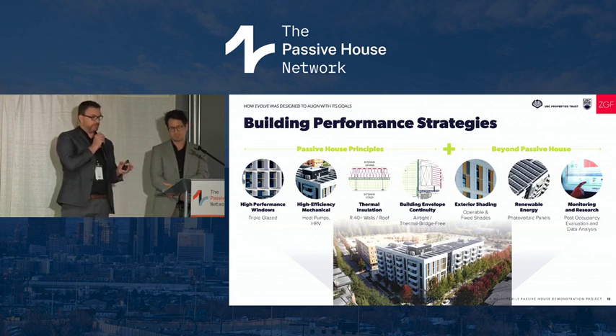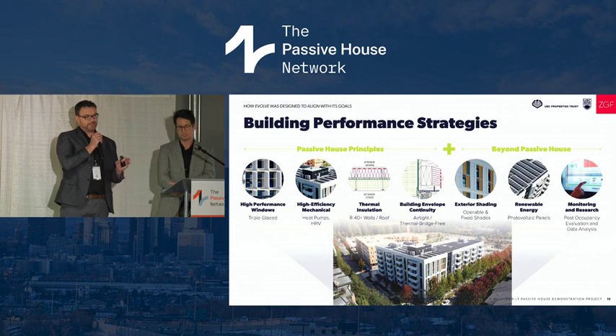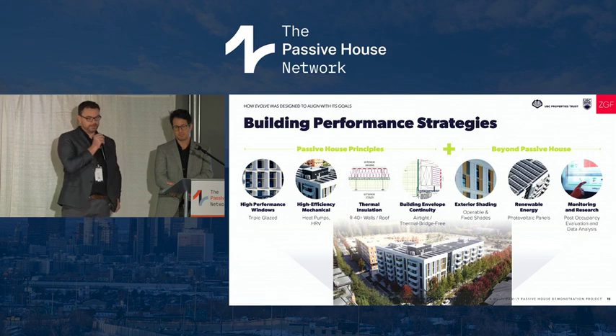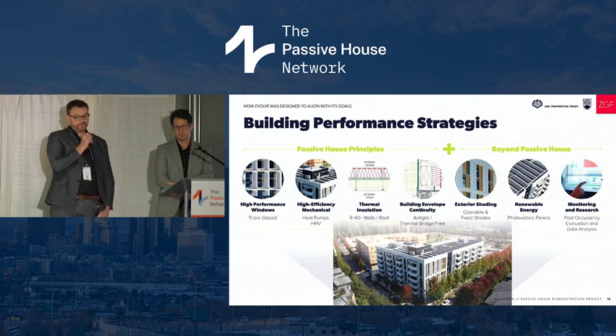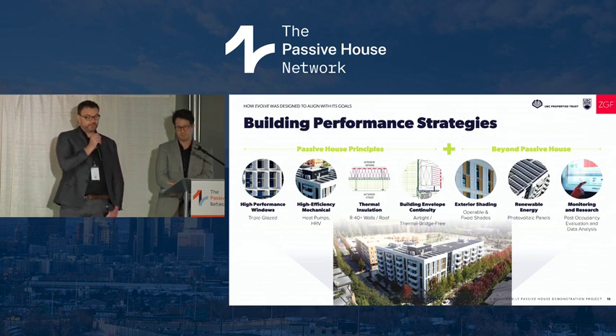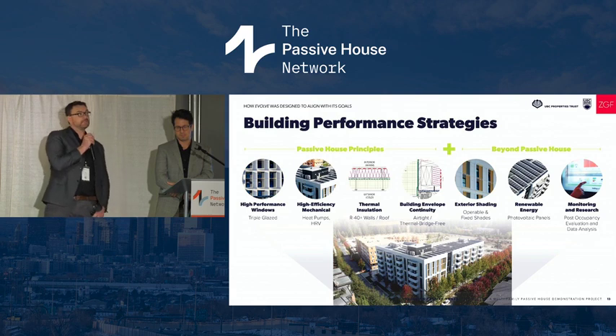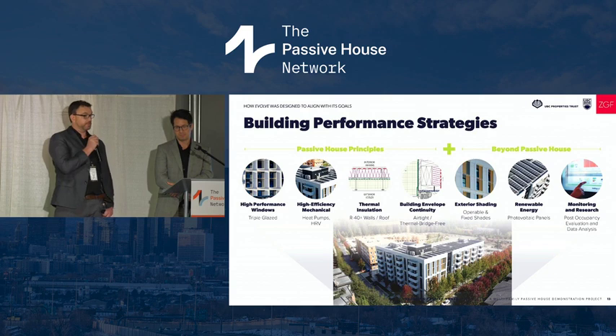Adam mentioned this Passive House Plus component. What we've tried to do is identify the core Passive House principles, but then go beyond that, which is the plus component. So we've got high-performing windows, an Intec triple glazed system, a highly efficient mechanical system with a semi-centralized HRV on the roof, with a post-secondary coil providing both heating and cooling to the airstream. It's highly insulated, with 6 to 8 inches of rock wool hung to the exterior, and for air tightness we managed to get 0.3 air changes per hour at 50 Pascal.